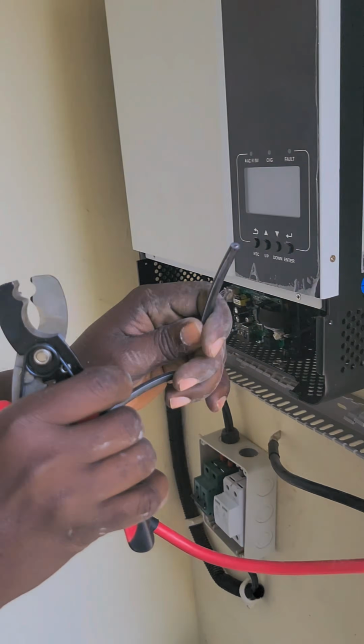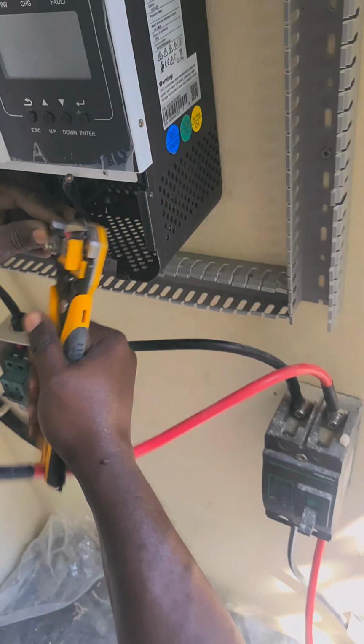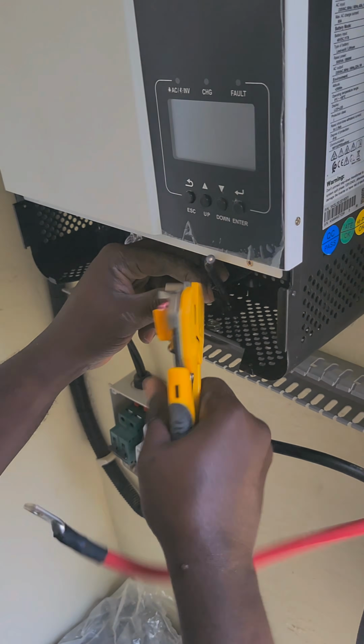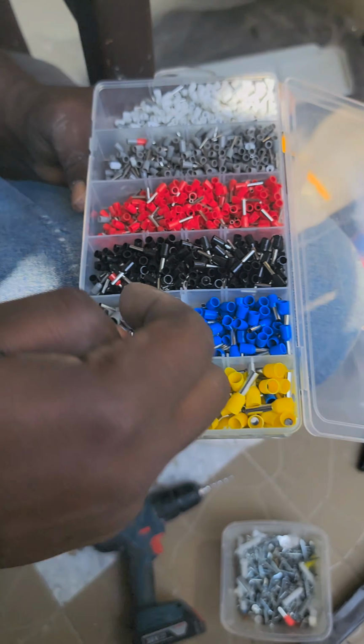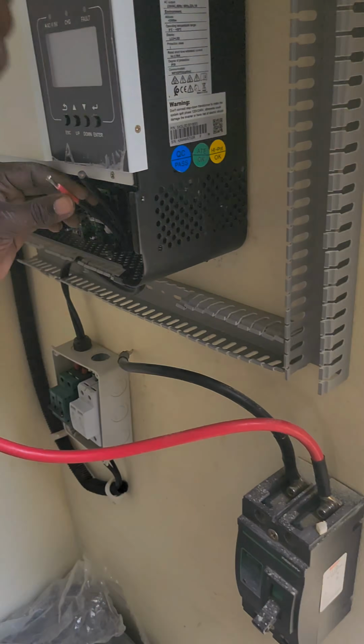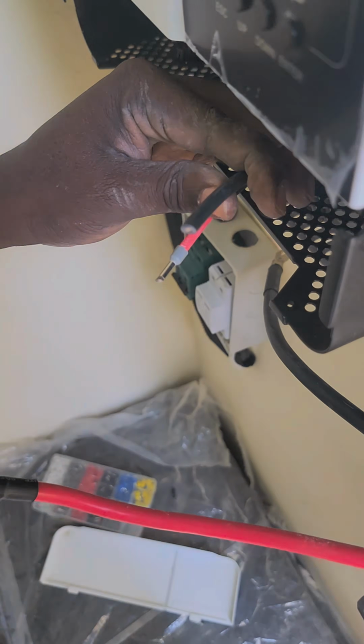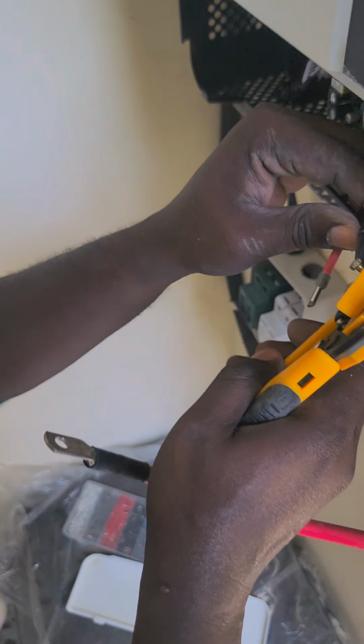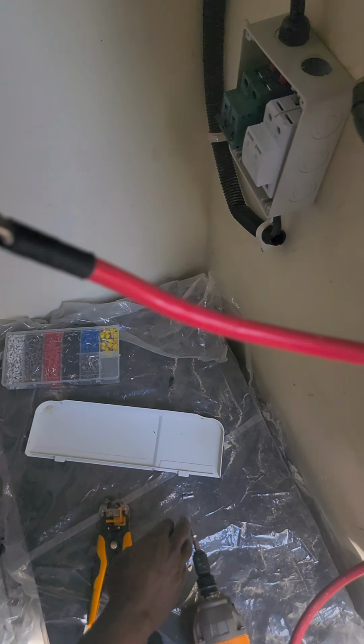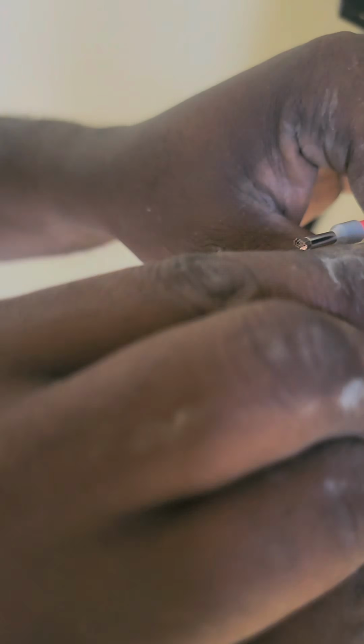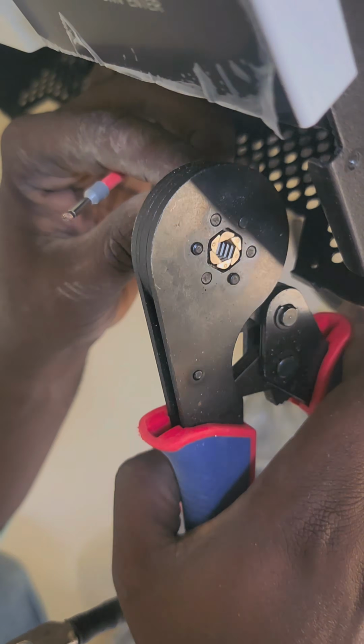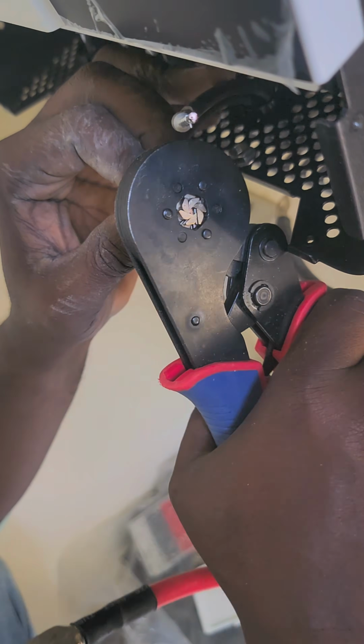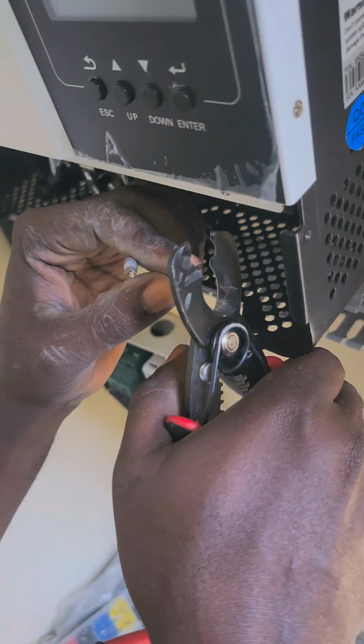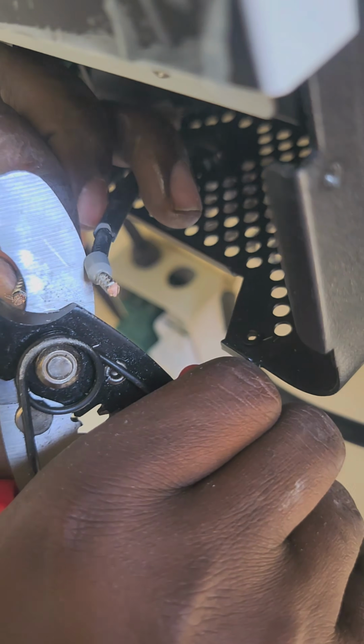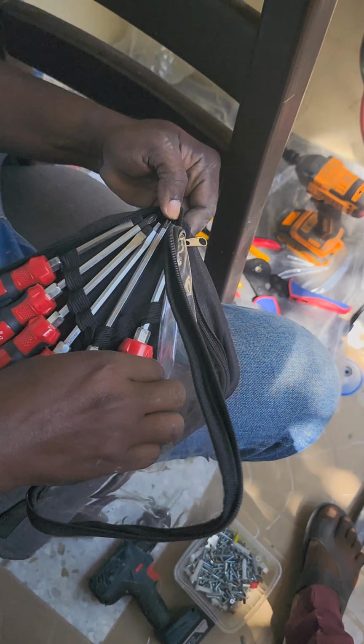Now I'm setting up the PV wire, preparing it to connect to the inverter, because this inverter has a built-in charge controller, so that's what we're using. This inverter is a high voltage PV inverter because it can take high voltage from the PV. In this case we're sending close to over 200 volts from the PV, because all 5 panels are connected in series. We're using Jinko panels, 580 watt Jinko panels times 5, all connected in series.